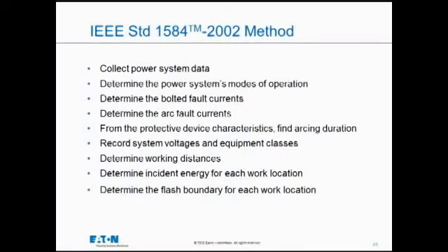and that goes into the equation. We determine working distances. How close would the human be to the type of equipment? There's some standards given for that. More or less at 600 volts or below, we're generally seeing the distance of 18 inches used. That's arm's length at your side, typical working away. The arc flash hazard is right at my fingertips and is coming at my face and chest. That's 18 inches away. Once all of that's done, the calculations can proceed to determine energy and flash boundary.